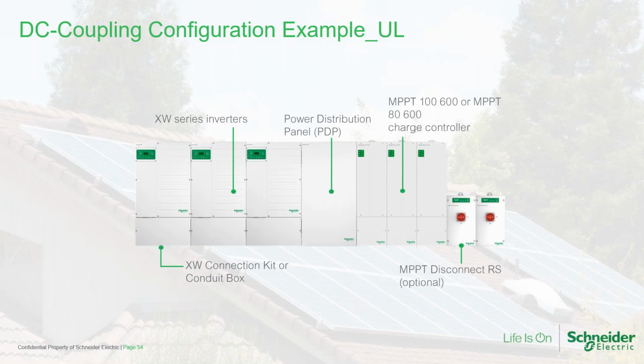Here's a sample system, DC coupled with arc fault rapid shutdown for rooftop solar. This may be used on-grid with a backup generator, or off-grid. Advantages of DC coupling include better efficiency when storing energy for use at a later time, and being able to monitor everything from a single platform.